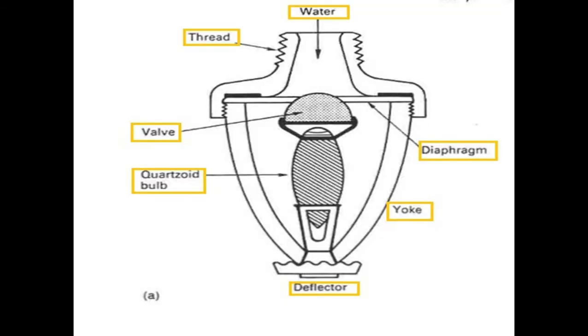Now you can look at the cross-section view of a sprinkler head. We have the inlet of water, the thread by which it is fitted to the pipeline, then the valve body, diaphragm, the quartzoid bulb, the yoke, and then the deflector, which deflects the water thoroughly. Whenever you are on board ships, you should always take keen attention and pay heed to even small nuances. When you look at all the small nuances, all these requirements will come into the picture together.